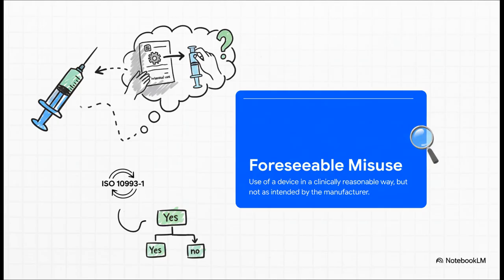Well, it's when a device gets used in a way that the manufacturer didn't intend, but it's still considered reasonable in a real-world hospital or clinic. That word reasonable is the key. We're not talking about something crazy like a surgeon using packing material as an implant. We're talking about predictable, everyday ways that people might deviate from the instructions for use.